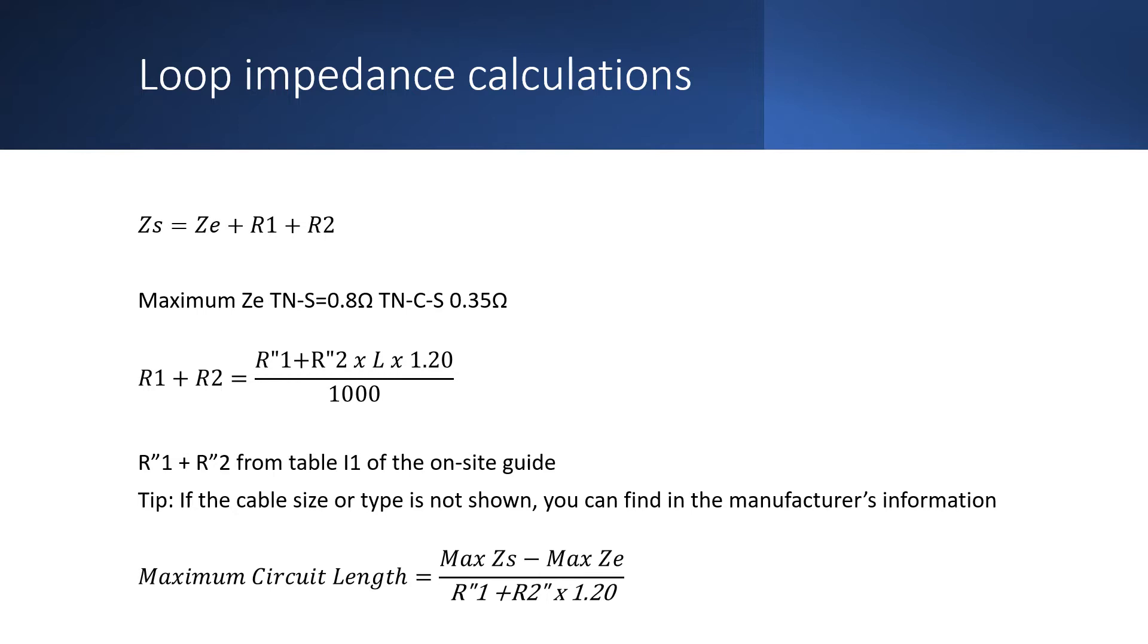When we are calculating the maximum length of a circuit it makes sense to use the maximum values for ZE. So 0.8 for a TNS system or 0.35 for a TNCS system. Even if we can measure the exact ZE, by using the maximum it will help us to ensure that the installation remains compliant over its lifetime.